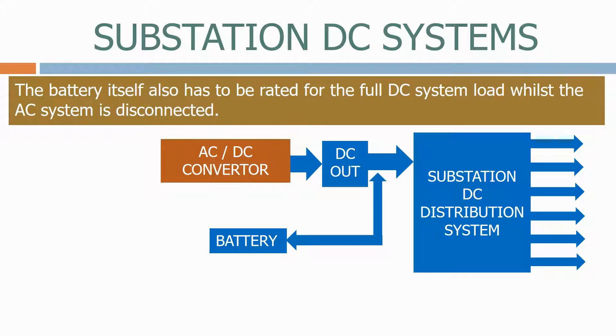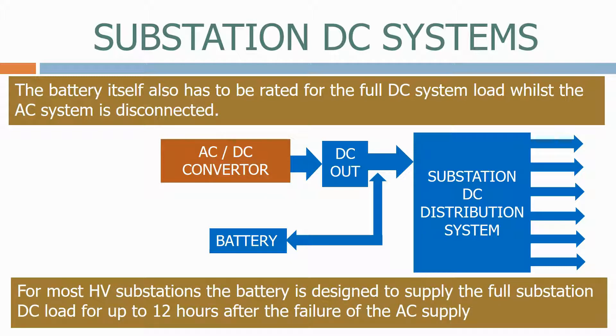The battery itself also has to be rated for the full DC system load whilst the AC system is disconnected. For most HV substations, the battery is designed to supply the full substation DC load for up to 12 hours after the failure of the AC supply.